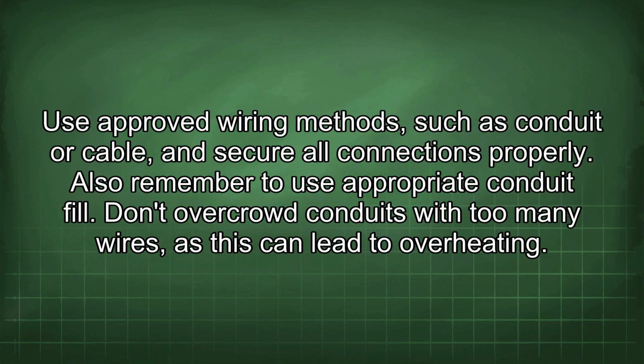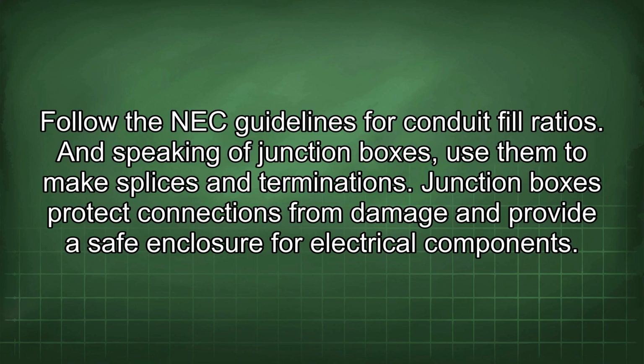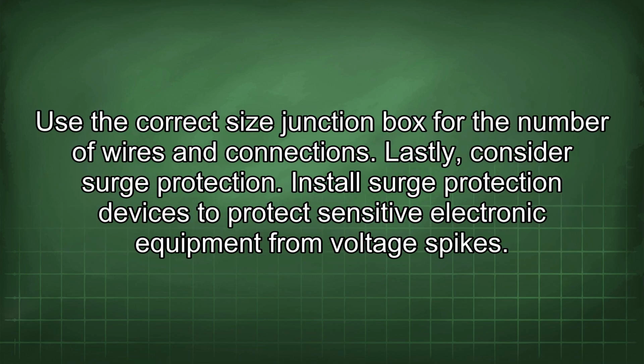Use approved wiring methods such as conduit or cable and secure all connections properly. Also remember to use appropriate conduit fill. Don't overcrowd conduits with too many wires, as this can lead to overheating. Follow the NEC guidelines for conduit fill ratios. And speaking of junction boxes, use them to make splices and terminations. Junction boxes protect connections from damage and provide a safe enclosure for electrical components. Use the correct size junction box for the number of wires and connections.